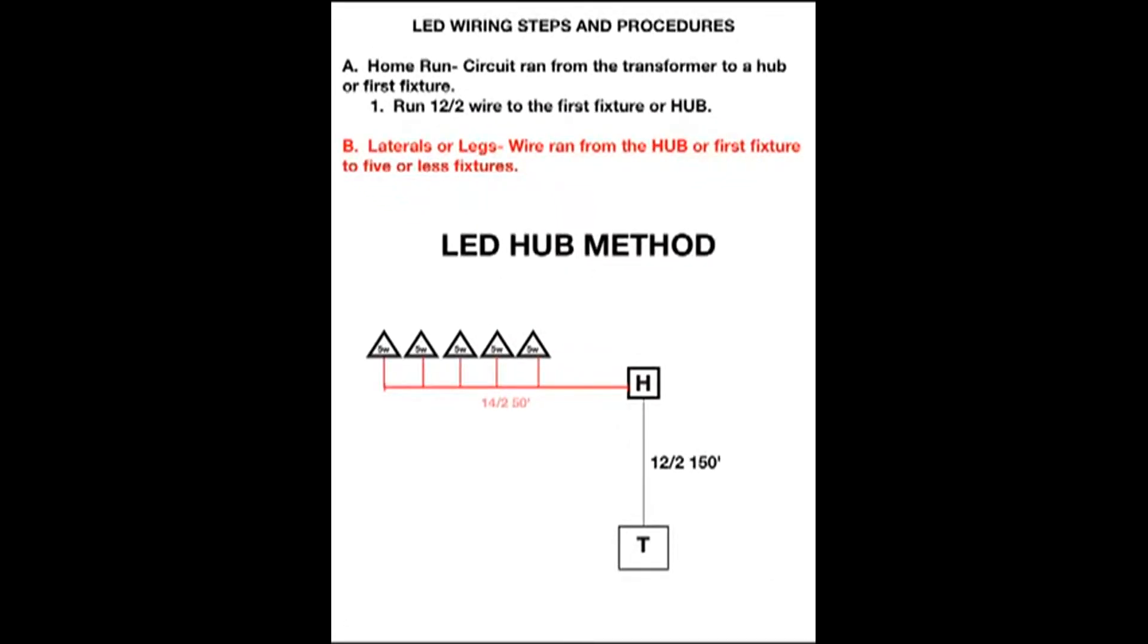Laterals or legs, that's a wire ran from your hub or the first fixture to five or less fixtures. Don't exceed five fixtures on each leg.